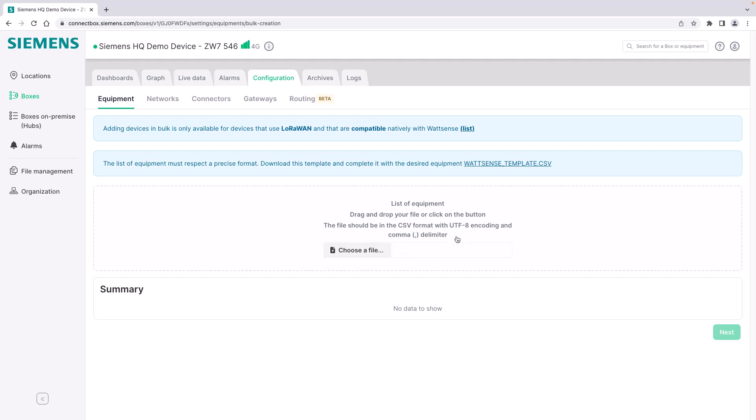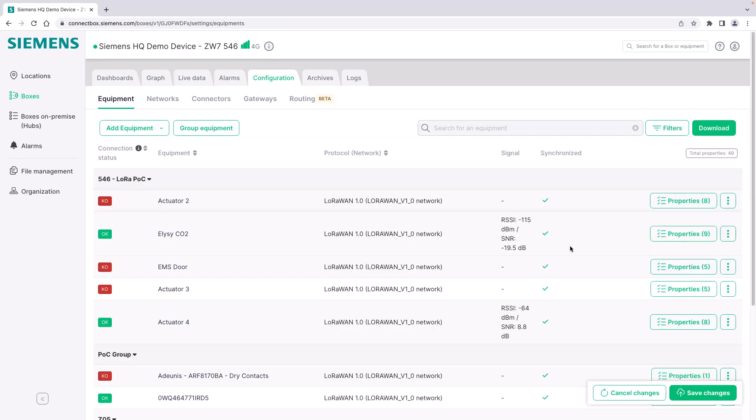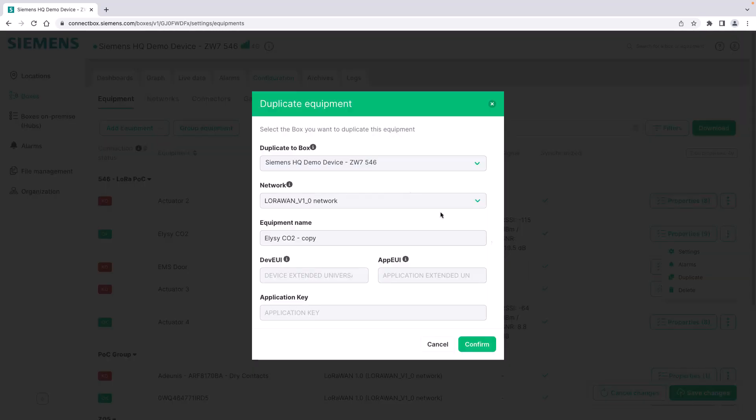In the described format the console is automatically adding all those equipment pieces to your connect box. This is definitely the fastest way when dealing with a lot of LoRaWAN devices. Last but not least you can also use the duplicate function to add new equipment. For example here I have the Elsys CO2 sensor, I can duplicate it, I add the new keys of this device equipment configuration, I confirm it and it is automatically added to my equipment list as an exact copy of the device that I had before including the properties.